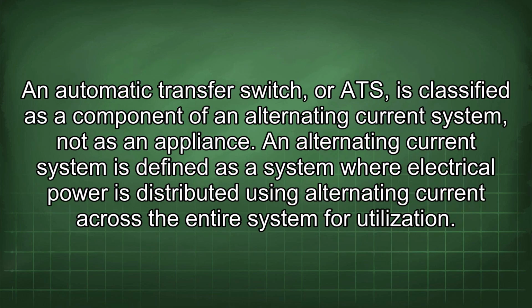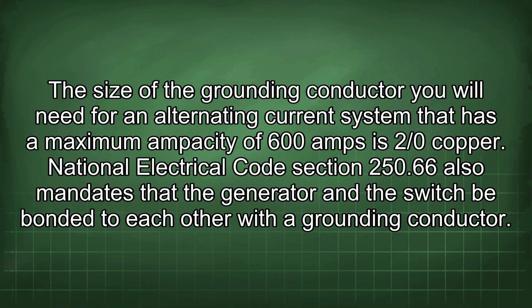An automatic transfer switch, or ATS, is classified as a component of an alternating current system, not as an appliance. An alternating current system is defined as a system where electrical power is distributed using alternating current across the entire system for utilization. The size of the grounding conductor you will need for an alternating current system that has a maximum ampacity of 600 amps is 2/0 copper.